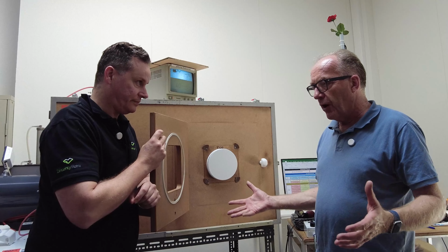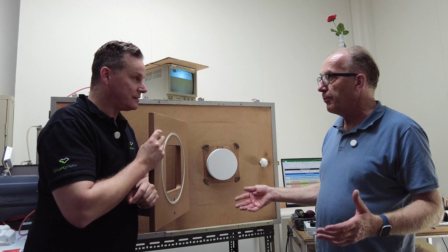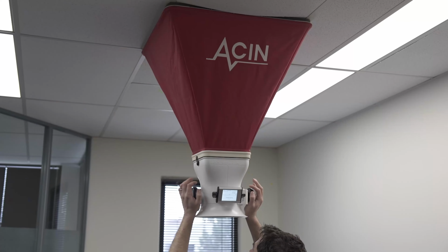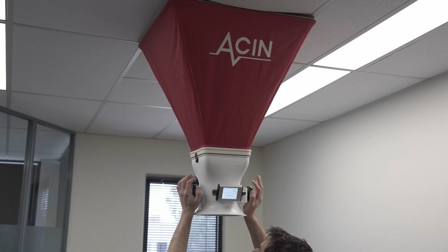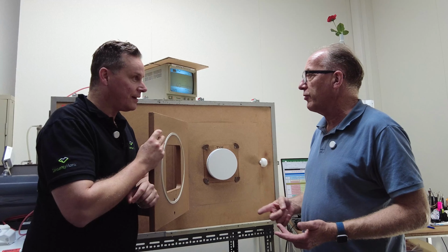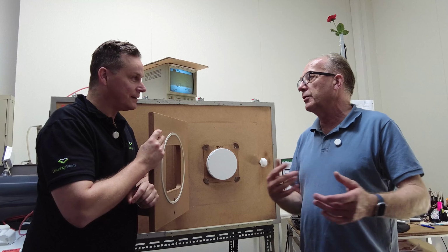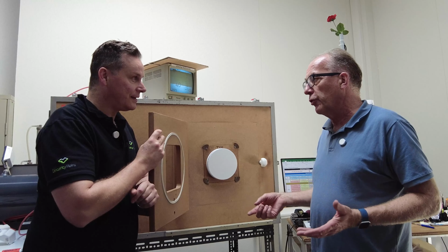You put it on the grill. The Flowfinder measures its own resistance, the pressure drop over the Flowfinder, and then starts running a fan. Like with a blower door. A blower door you would control to, let's say, 50 Pascal or 10 Pascal or whatever. The Flowfinder you always control down to 0.